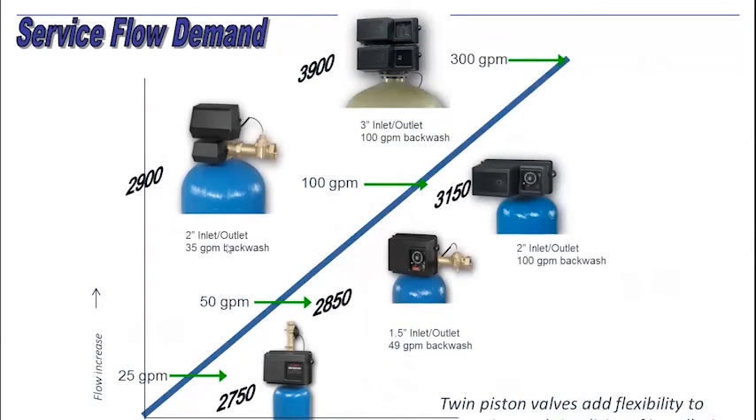You have the 2-inch 2900 valve. It has 35-gallon per minute backwash but handles that 100 GPM flow rate. It's able to network with other valves and work in tandem — work in what's called progressive flow. The 3900 steps up to 300 gallons per minute with 100 GPM backwash. Both of these valves can handle a great complexity of issues. They're really geared at water softening and lighter filtration needs. When you get into Corosex and Birm, you'll need to modify the practice a bit. These are geared for the bulk of softening and filtration applications on the market.